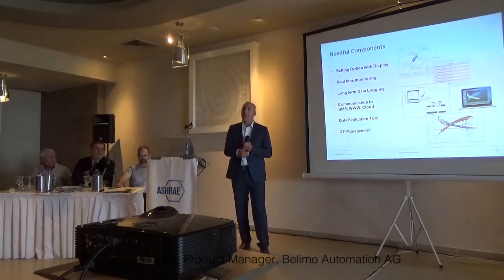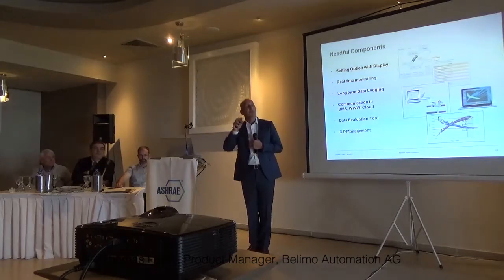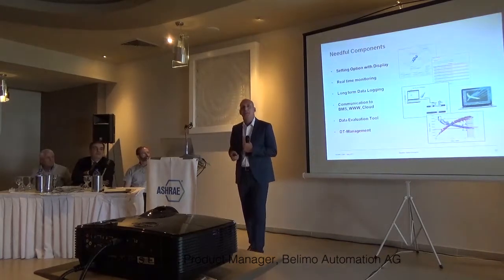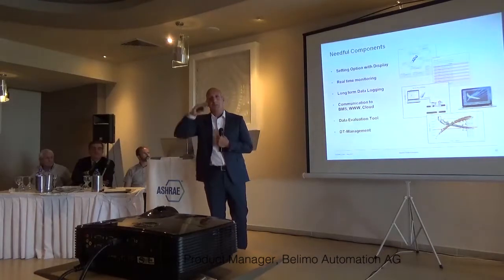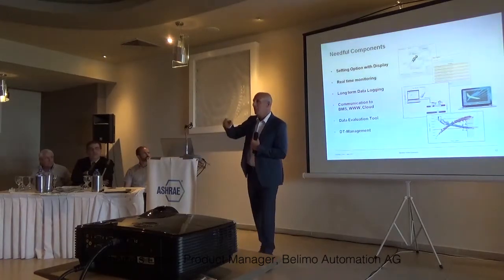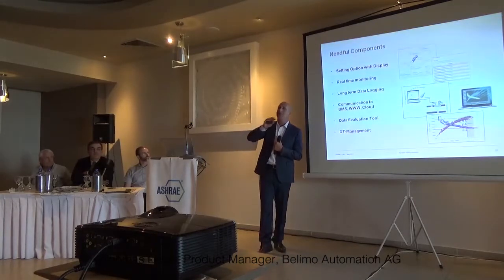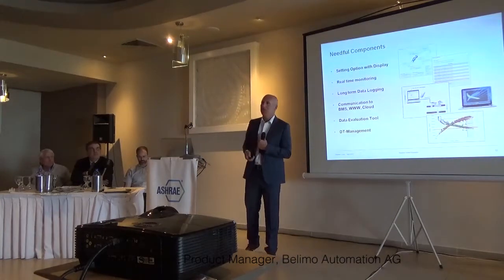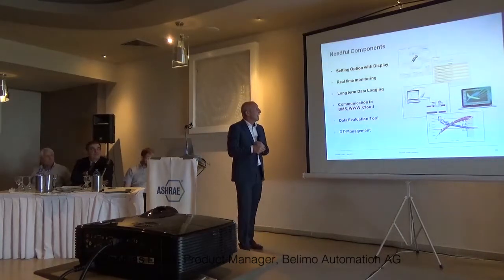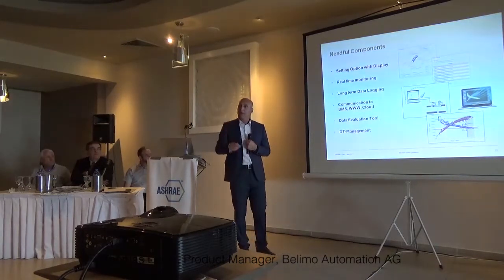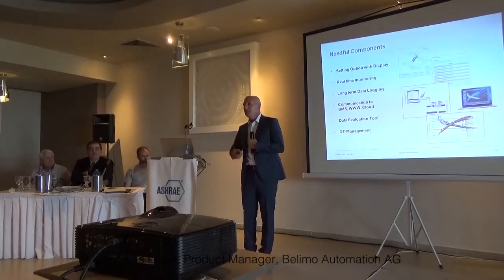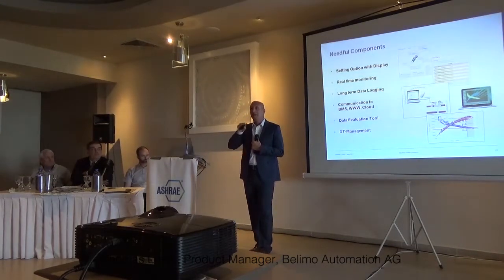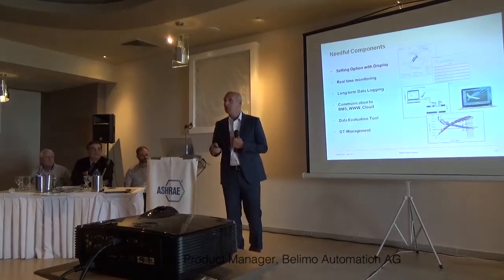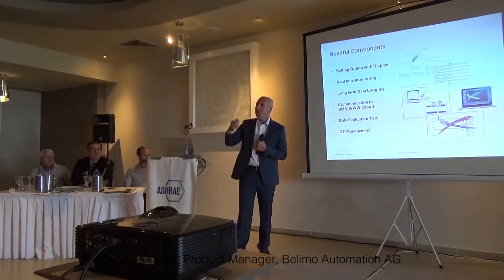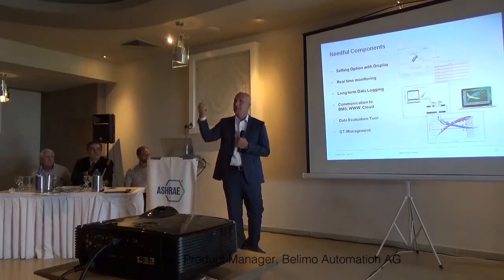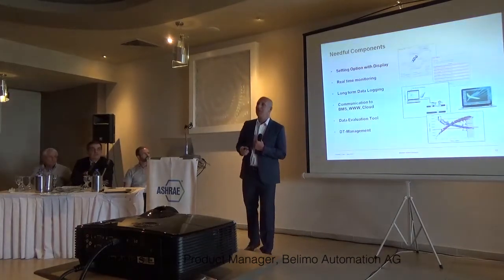Communication to BMS. Modern valves should be able to communicate in an easy way to the BMS or a superior position. BACnet, Modbus, all these should be kind of standard. Come just with the valve. What is coming more and more is remote access. Either, if you have the VPN, through the internet, or what would be even better, go through a cloud with applications where you can definitely immediately point what you need to have.